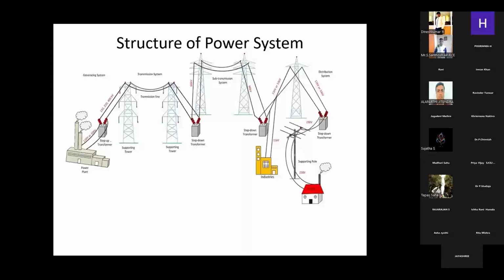We have different types of transmission systems: primary transmission and secondary transmission. In primary transmission, the voltage is stepped up to 132, 220, or 400 kV, then transmitted over long distance at high voltage to reduce the I squared R transmission losses.